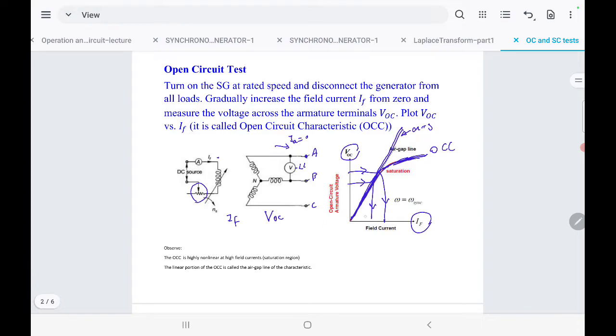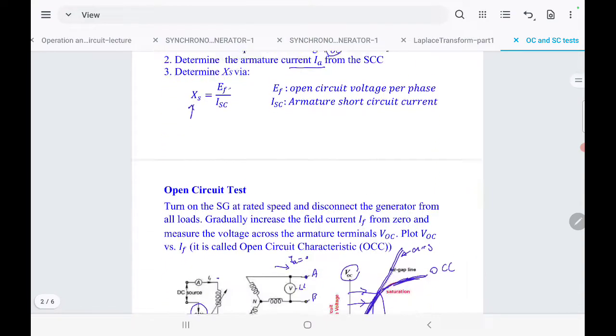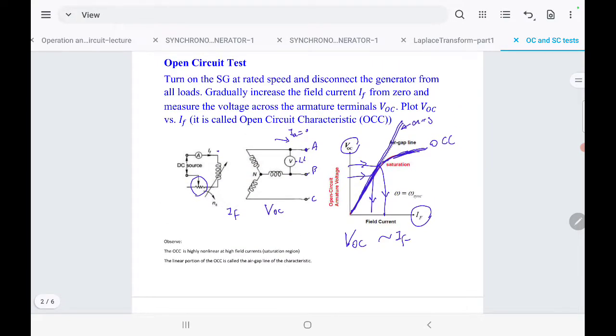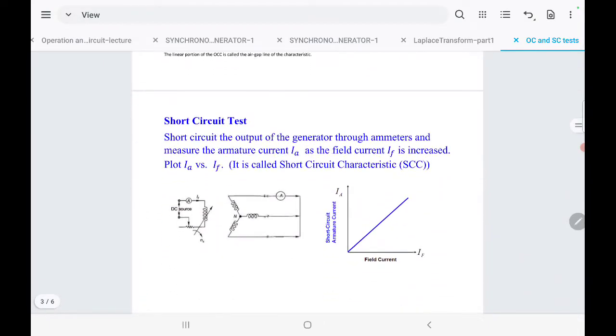From the open circuit characteristic, at any open circuit voltage you can find the corresponding field current IF. Going back to the equivalent circuit, when the circuit is open the armature current is zero, so the terminal voltage equals EF. That is the purpose of the open circuit test — to measure VOC. Remember this is line-to-line, so divide by √3 to get the phase voltage EF.